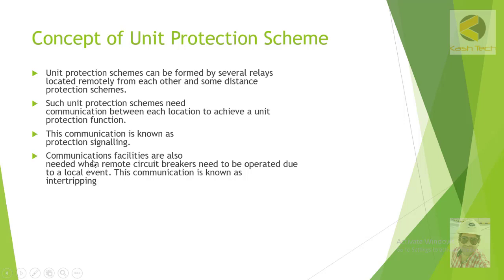Communication facilities are also needed when remote circuit breakers need to be operated due to a local event. This communication is known as intertrip or control tripping. These are the basic definitions: unit protection scheme refers to protection of a defined unit such as a transformer or a line.